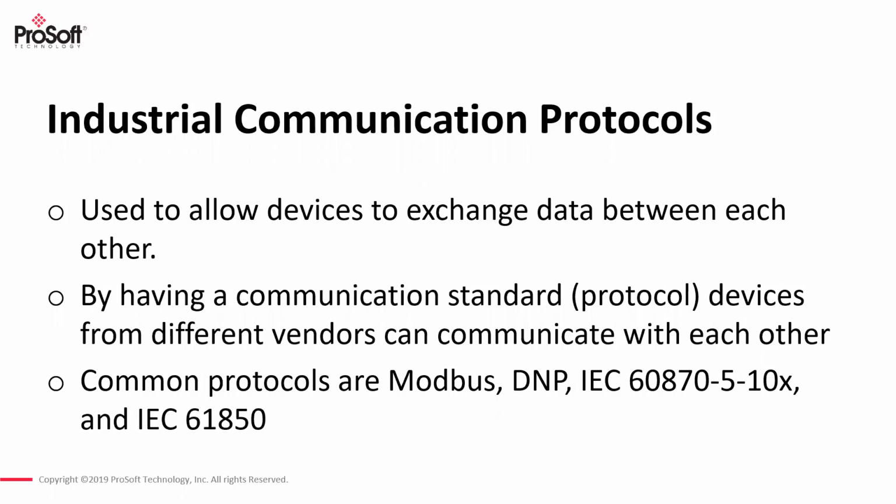Specifically, in some power generation and distribution applications, there have been some common protocols over the years. Protocols such as Modbus, DNP, IEC 60870-5 101, 103, 104, and now IEC 61850 have really dominated the space for IEDs in power generation and distribution applications.